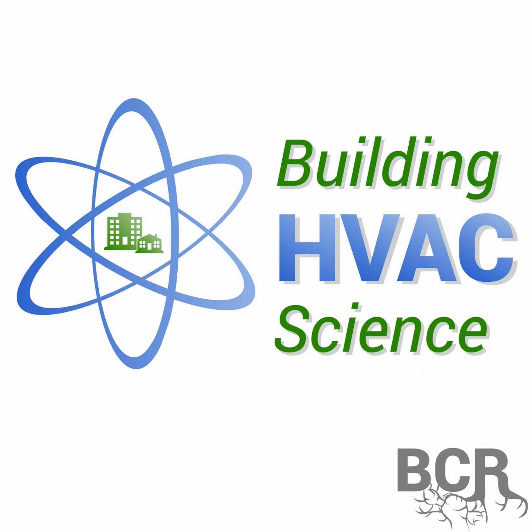You actually need two temperature measurements, one before and one after whatever system component is heating the air, for example, the heat exchanger or strip heater. So this still isn't too bad, but temperature does not equal airflow. So you need an equation to go from your temperature to your airflow. So your equation is CFM equals the BTUs per hour divided by 1.08 times delta T. So CFM is cubic feet per minute. That's the number you're after.